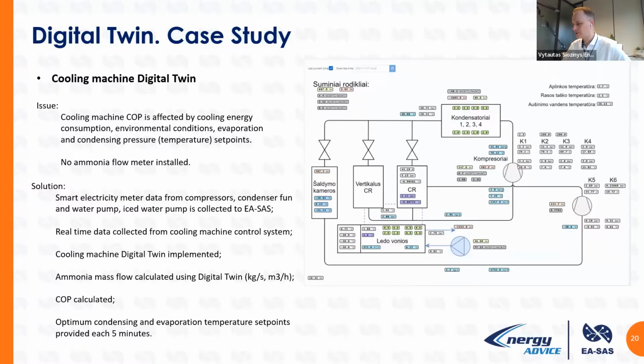The temperature of the cooling water is 2 degrees supply, and this example is real live data from November 17 at 2 o'clock p.m. And the second loop is the compressor. 2 compressors are working to the refrigerators at -20. The second is disconnected, and then another at -21. So it's this cooling chamber, which cools down product in fast cooling mode.